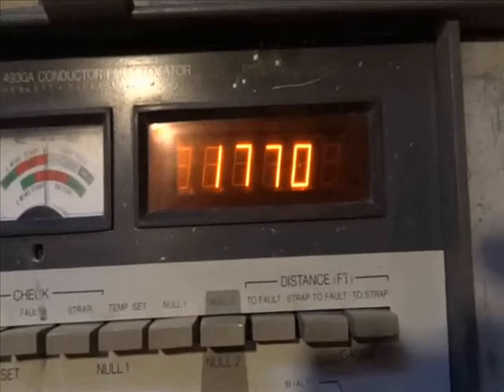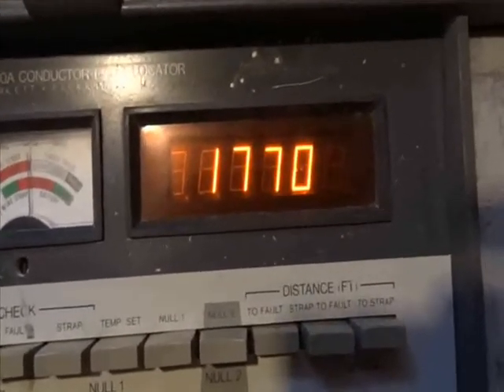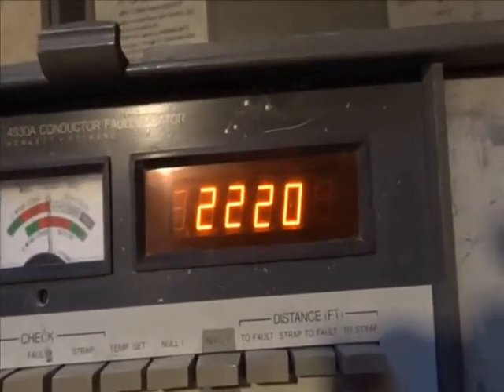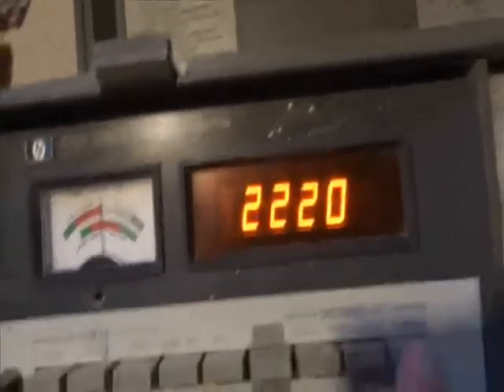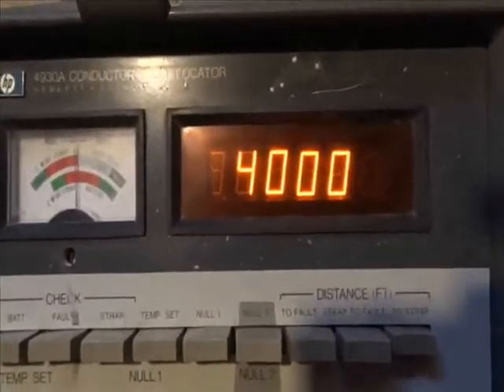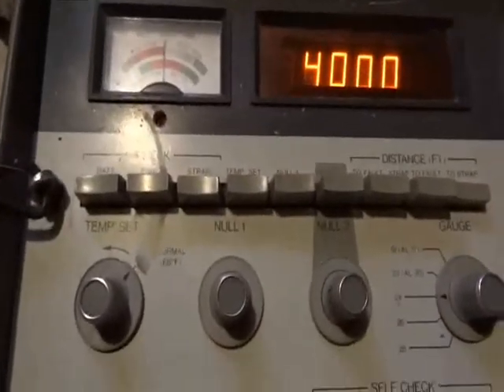Should be about 1,800 plus or minus 20, and we're pretty close. Strap to fault should be 2,200 plus or minus 20 — we're in the range. And to strap, it should be 4,000 plus or minus 30, and we're 4,000 on the nose. So the calibration looks okay, and this is ready to go.